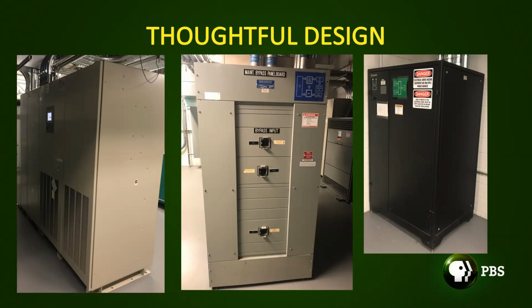What the STS does is it has both power buses available inside, and it monitors them both. It normally runs on power system 1, but if power system 1 is having trouble, the STS is pretty sensitive, and it will seamlessly switch over to power system 2. That keeps our single cord devices running.